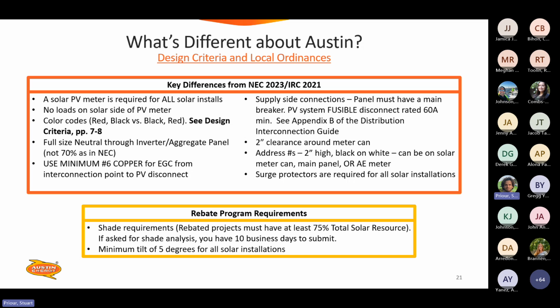And you need a full-size neutral through your inverter or your aggregate panel, not 70%, as national code would allow. Also, you've got to have a minimum number 6 copper for your equipment grounding conductor from your interconnection point to the PV disconnect. After which you can refer to the NEC for required equipment ground sizing. For supply side connections, the panel must have a main breaker. It's got to be a fusible disconnect and rated a minimum of 60 amps.